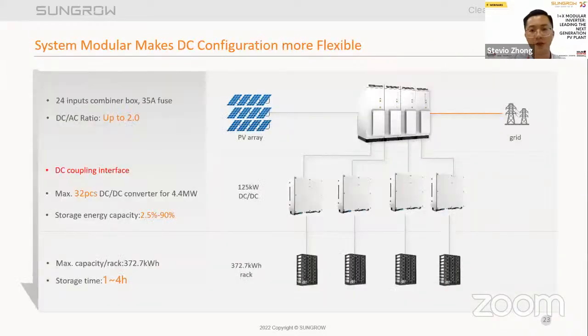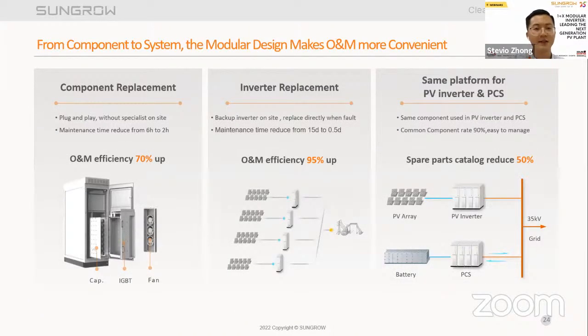System modular makes DC configuration more flexible. The maximum number of input for the combiner box is 24, and reaching DC-AC ratio up to 2.0. The 1+X modular system has a DC coupling interface, which is for BESS extension, which helps to save much cost for the project. From component to system, the modular design makes operation and maintenance more convenient. From the left picture, in the component level, key components are in modular design, such as capacitor, IGBT, and fan. So specialists are not needed in the project site.